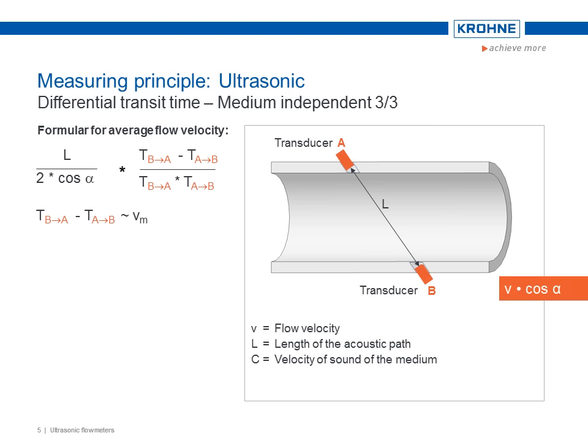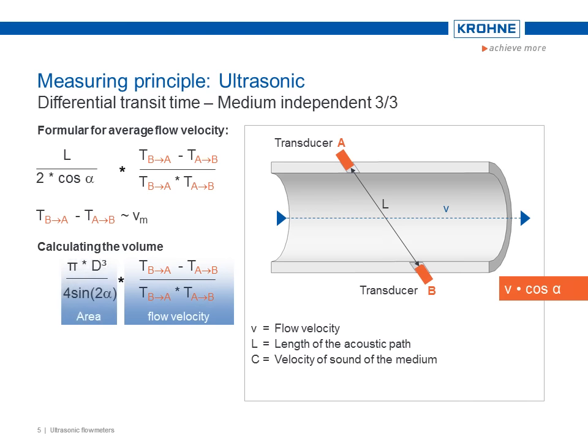Equations 2 and 3 combine to result in the formula: path length divided by 2 cos alpha multiplied by the transit time. This represents the average flow velocity. When multiplying the average flow velocity with the cross section of the pipe, we get the flow rate Q.